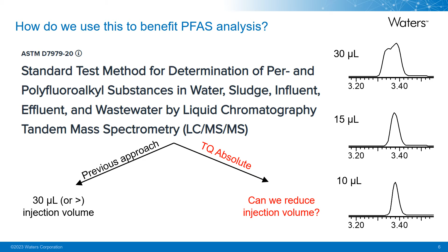There are also some other benefits to reducing the injection volume, including increasing your column lifetime because we're not injecting as much matrix onto that column, as well as less user interference with the source to do source cleaning, again, because we're reducing the amount of matrix we're introducing to the system.